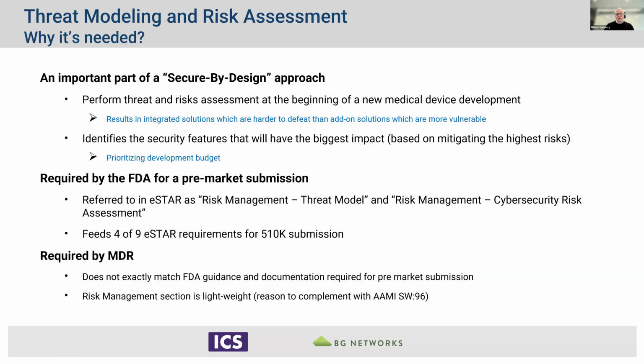From the EU MDR perspective, this doesn't exactly match what the FDA is doing in terms of documentation for pre-market submission. The risk management is a bit lightweight, which is why it can be supplemented with SW96 from the AAMI.